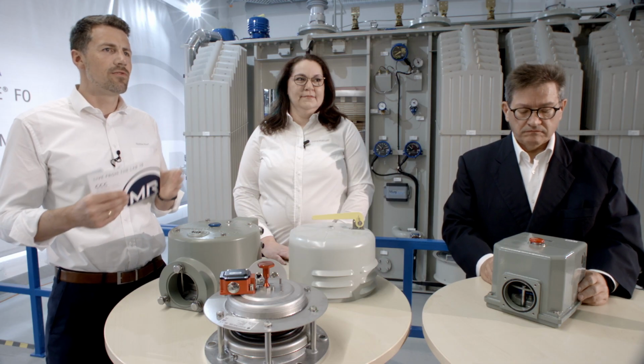When talking about protective devices, we basically need to differentiate into three main groups necessary to protect a power transformer: protective devices to secure transformers from overpressure, so-called pressure relief devices (PRDs); gas relays, so-called Buchholz; and last but not least, further protective devices, for instance shut-off valves or gas collecting devices. So we are looking forward to the upcoming minutes.